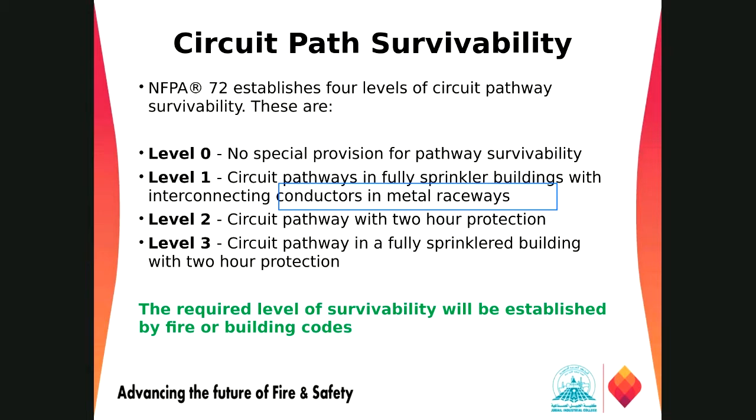Now, where did this requirement come from? It came from the life safety code and the building codes. For example, healthcare occupancies, such as hospitals, might need level 3 or level 2 protection. Other occupancies, such as warehouses, might need just level 1, not level 0. Level 1 just puts the conductor in a metal raceway to protect it. Those requirements come from the International Building Code, IFC, or the Saudi Building Code and so on.